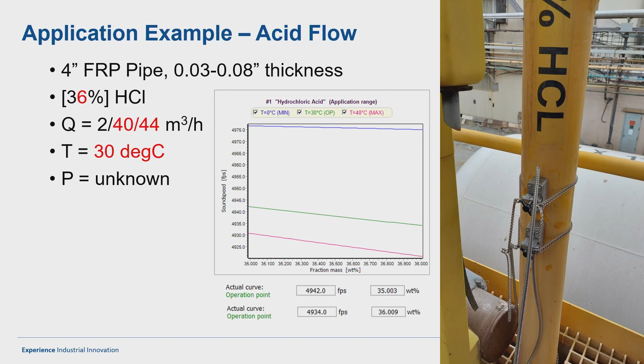He told us 9.4 millimeters - I have no idea what that number is because I don't understand small metric values. But he made it sound like it was very consistent. When we went to measure the thickness, it varied from 30 thou to 80 thou of an inch. That can make it very difficult for a clamp-on ultrasonic meter, because we're now talking about different thicknesses that the sound wave has to move through.